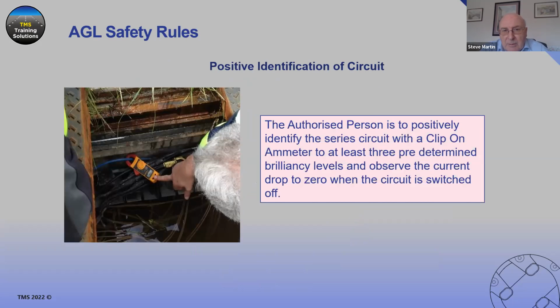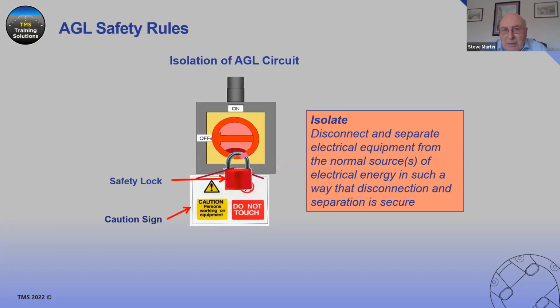Okay Keith. Yeah, so this - we can then isolate the circuit. This is one LV switch disconnector, but it's in the off position, safety locked. This one's red to clarify that it's being used for safety. The key's been removed and we're going to put that somewhere safe. And then we've got a caution sign on there that tells anybody that there's people working on the equipment and they shouldn't interfere with it.